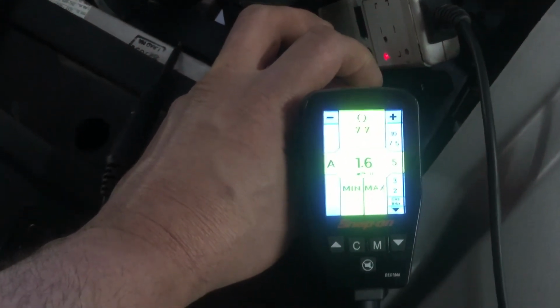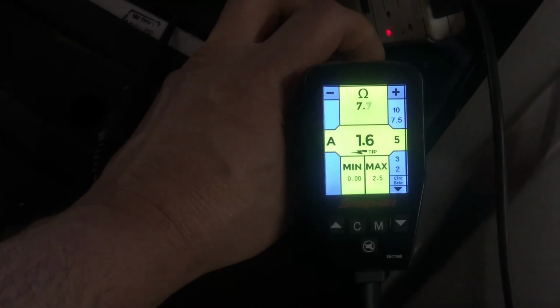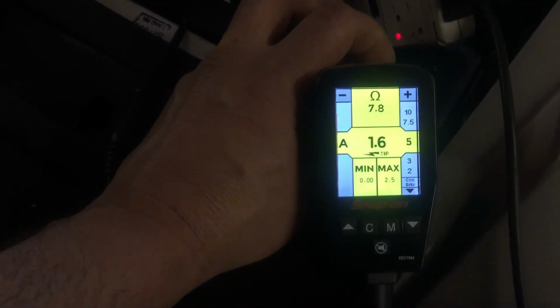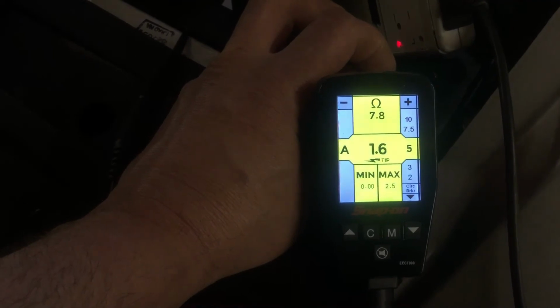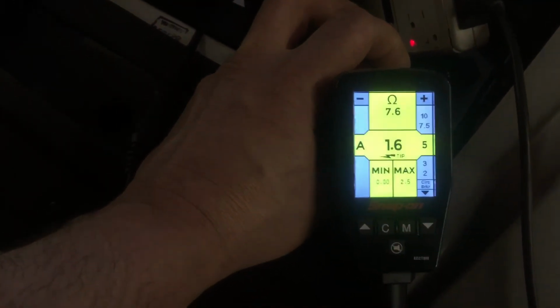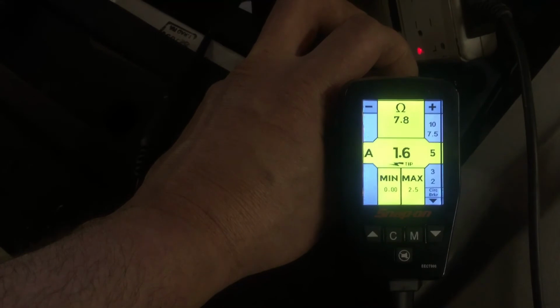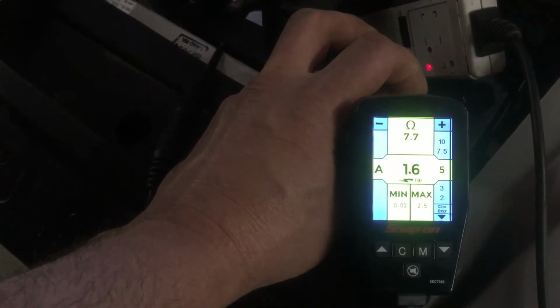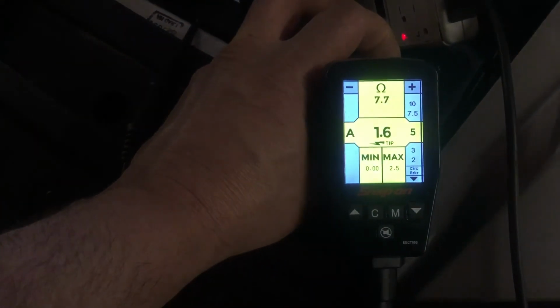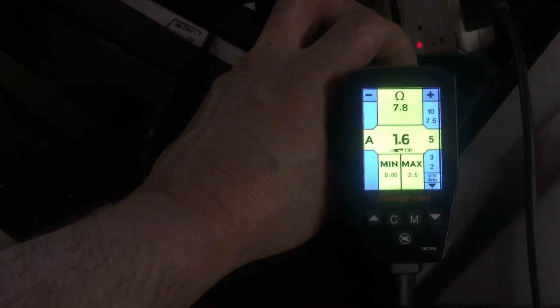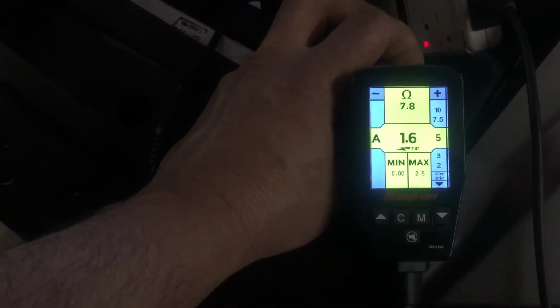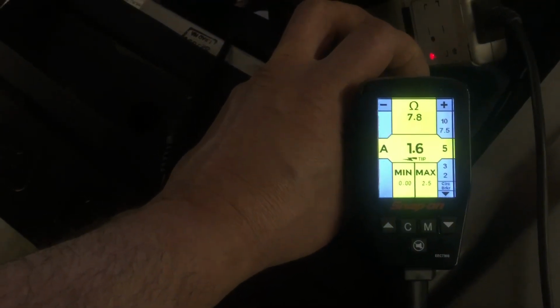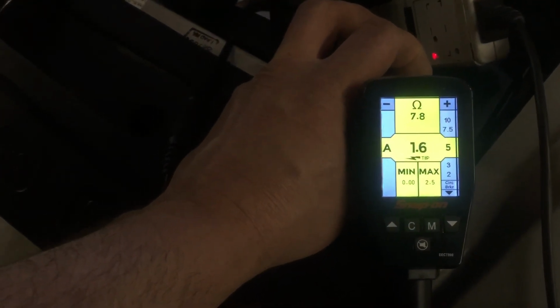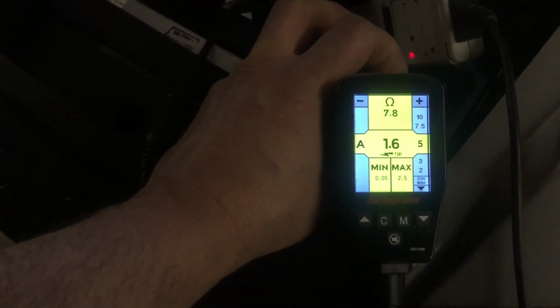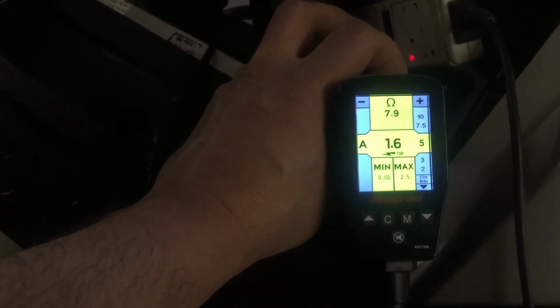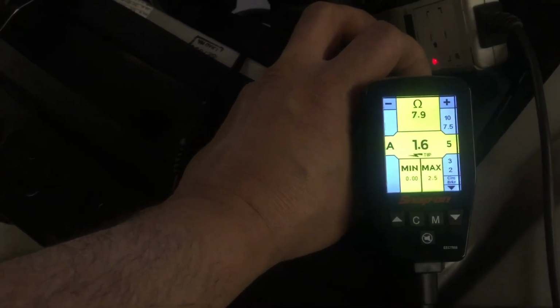I think most of us know that for diagnostic purposes, resistance can be useful, but in a circuit that's not functioning, it's fairly irrelevant because we haven't considered current flow, temperature coefficient, and if we just measure the resistance of this motor and do some math, it's going to look like it has a huge current draw, which it does at startup, but then you have to consider other factors for running current. So it's my little 'ohms is a liar' discovery with the current on the power probe.